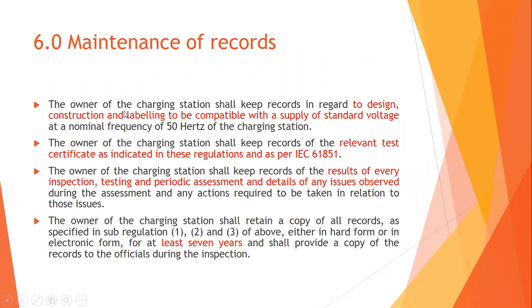Rule 6 covers maintenance of records. The owner of the charging station shall keep records regarding design, construction, and labeling compatible with the supply standard voltage at normal frequency of 50 Hz. Records shall include the test certificate as per IEC 61851, and results of every inspection, testing, periodic assessment, and details of any issues observed along with actions required. All records shall be retained in hard or electronic form for at least seven years and a copy provided to officials on duty inspection.